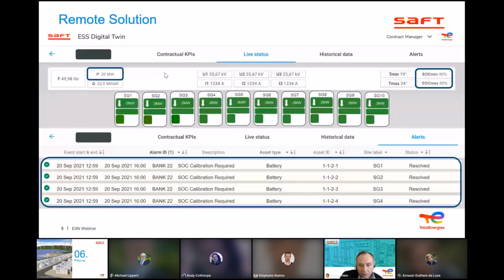Now, the reason that led the battery strings to be out of calibration in this case was continuous operation and cycling of the battery with no dedicated time for a recalibration scenario that is required in the operations manual. Now, as described in the manual, the short routine should be carried out during the low or no demand periods to avoid the power limitation that was highlighted here.